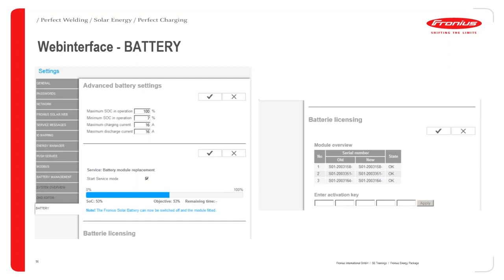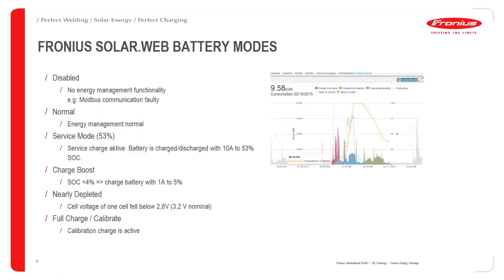Then you've also got your battery service module replacement. If you replace a module or you add a module, then it needs to be put into service mode, because when the replacement or new battery module comes, it's always at 53% state of charge. So in order to place that into the battery unit, you need to have all the rest of the modules at the same state of charge. When you trigger that, depending on whether you're allowed to export to the grid, whether you've got load on, or whether the batteries need to be charged because they're below 53%, and depending on whether you've ticked charging from the grid or not, it will charge up to that state of 53%. So that's that part there.